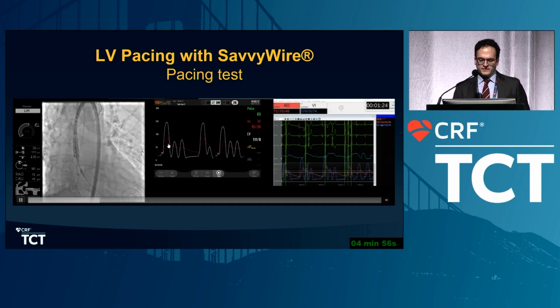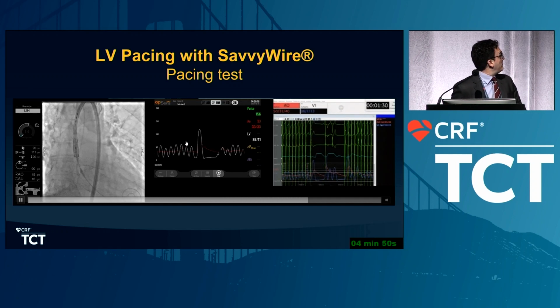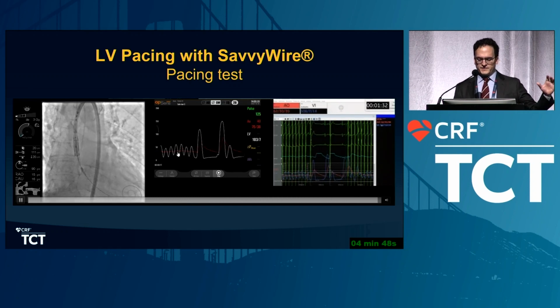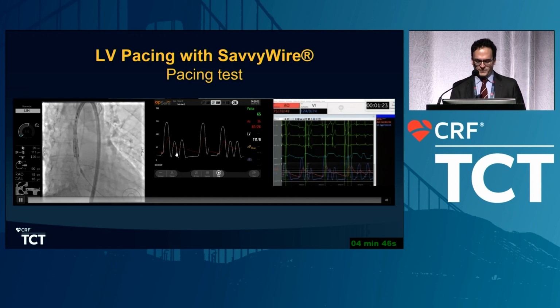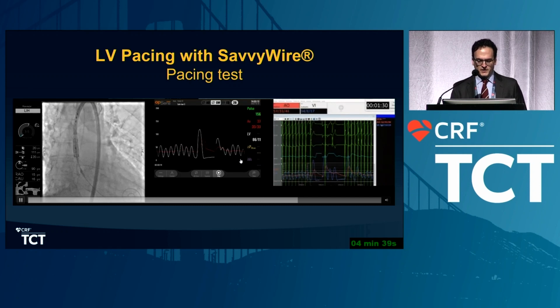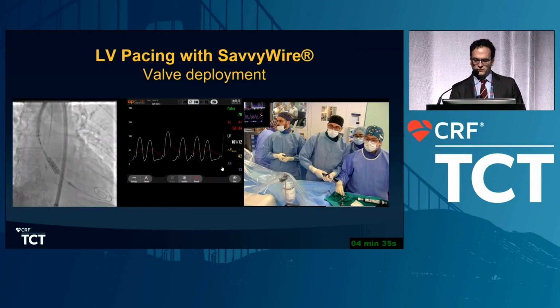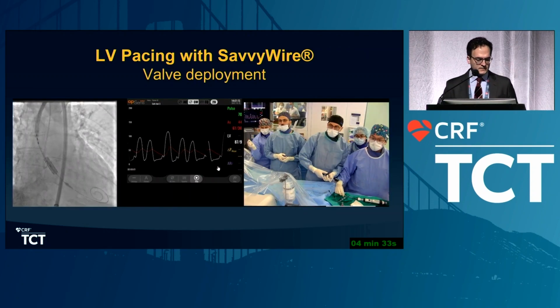And you're looking at the live pressure, which is in the pigtail, and the pressure inside the ventricle. And you can see that there is a nice pressure drop with the pacing test, that the pacing test is stable, and you can see here that the pressure drops below 50. So if you're happy with that, then you can move on to do the valve implant.